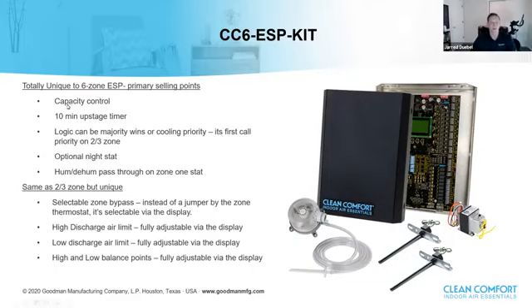So first of all, capacity control. Just like the Comfort Bridge system can upstage the multi-stage system without the need of a multi-stage thermostat, our zone control panel can do that as well. Although it may not be needed when you're installing on a Comfort Bridge type system, in any other application, if you have a multi-stage piece of equipment and you want to use single stage thermostats, you can. Capacity control is just a set of dip switches where we can set a minimum number of zones calling. Whenever we reach that threshold, we're automatically going to upstage the equipment.